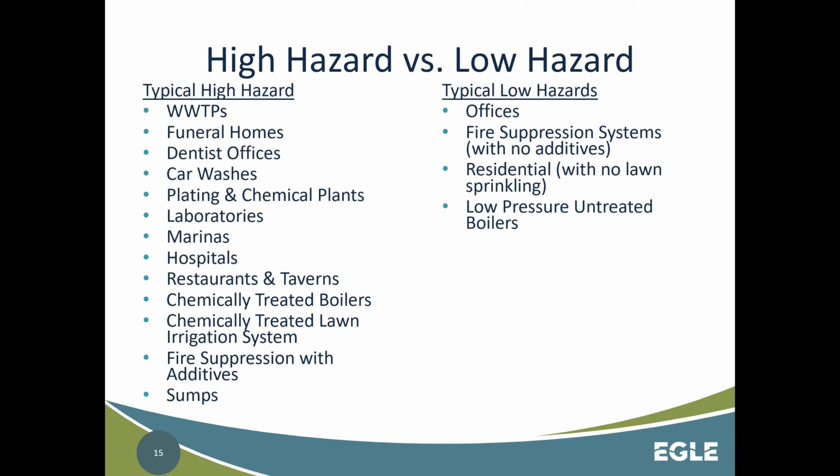Funeral homes. Yes, funeral homes are definitely a high hazard, and that's because they use aspirators, which are hooked to water systems, to embalm bodies. All right. Dentist's office, because of just the way they sanitize their equipment, their drains, and all that stuff. Car washes, plating and chemical plants, laboratories, marinas, hospitals, restaurants, and taverns, mainly because of the dishwasher solutions and stuff like that.